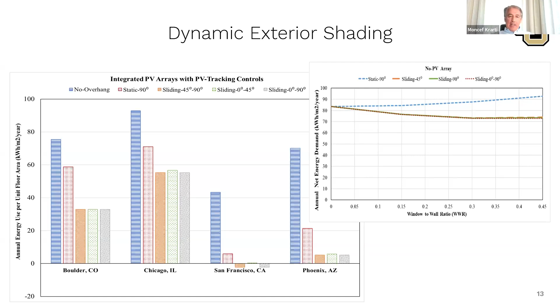We went even further and tried to use these two ideas of what we call dynamic envelope systems, integrating them together in an office building. So we're using what we call adaptive envelope systems. In addition to the dynamic insulation I mentioned, which we can deploy in the wall, ceiling, or roof, we can even adopt this technology in the floor, giving us a variable and dynamic insulation level. We also have what we call dynamic windows, or smart glazing, switchable glazing with different tint as well as different R value, in addition to the PV-integrated overhang I mentioned before.